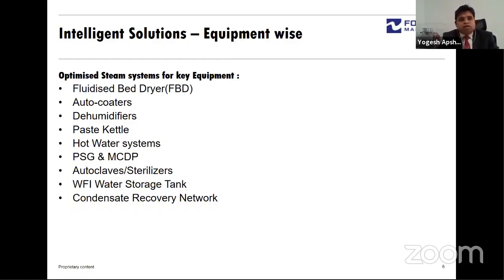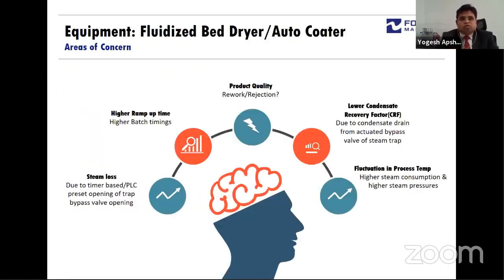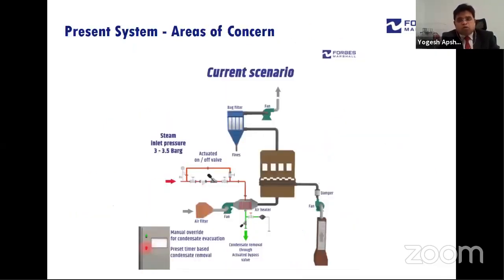So we have put down our analysis, areas of concern, and the next generation, or intelligent, steam systems for these applications. To begin with, the fluidized bed dryer or autocoater. The top five things that come to our mind when analyzing the vast data are these. There are huge steam losses, because preset parameters on the control panel or PLC open the bypass. Then higher ramp up times: in peak winters the operation starts from 10 or 15 degrees and has to reach the process temperature, so you take higher batch timings. Then product quality, which at times has rejection or rework. Then a lower condensate recovery factor, because of the steam trap bypass being open. These are the typical problems we have observed in fluidized bed dryers and autocoaters.